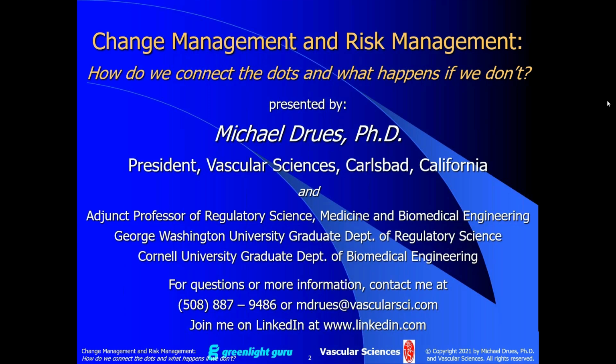So again, it's a little difficult to answer in a very general or ubiquitous sense, but the first thing that I would be asking is how, if at all, that change is going to influence the results. And then step two is taking this to the FDA prophylactically. I would not do it in your submission. There's no better way to just put a red flag on the top of your submission and say, FDA, don't even waste your time reading this, just throw it right back at me. I would take it to them probably in the form of a pre-submission meeting and make sure that they see that change as, if I say the word not significant, it's going to confuse people like a significant risk device, but it's not a significant change in the change management and risk management sense of the word. I hope that makes sense, Andrea. If you want to ask a follow-up, please feel free.